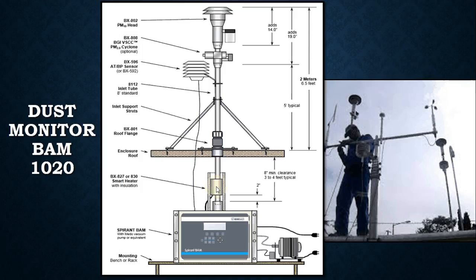There are many options of input to this dust monitor, namely AT, atmospheric temperature, RH, relative humidity, PM10 or PM2.5 dust inlets, PM10 real-time module, and wind sensors. The picture on the right shows the inputs connected to a walk-in shelter BAM 1020 units. This picture here shows that's the wind speed, that's the wind direction sensor, that's the PM10 inlet, that's the atmospheric temperature, and so on.